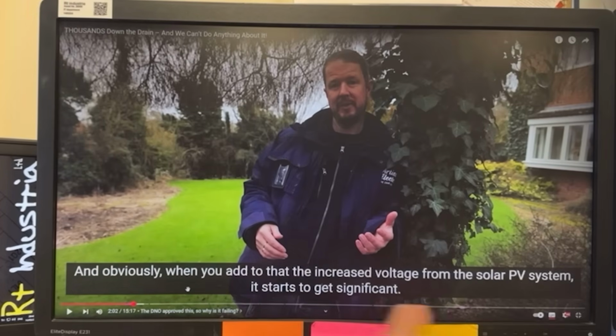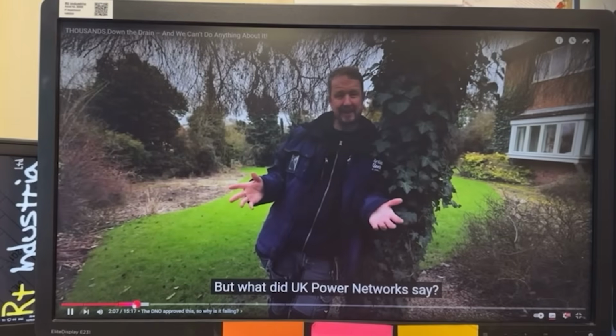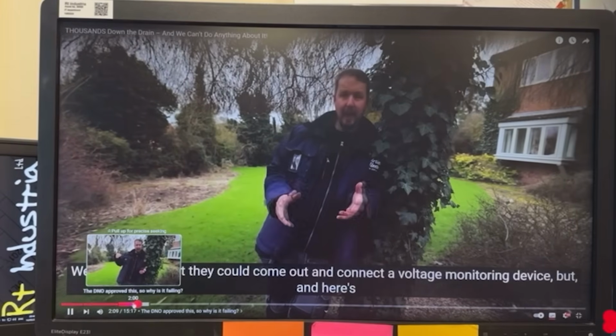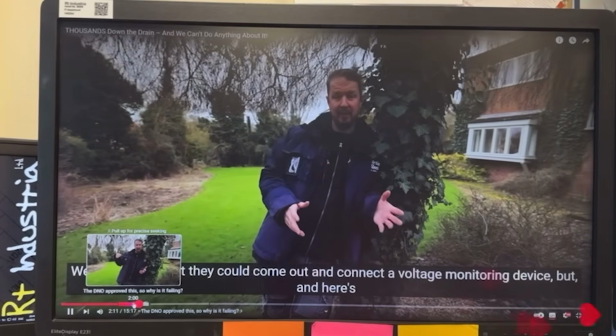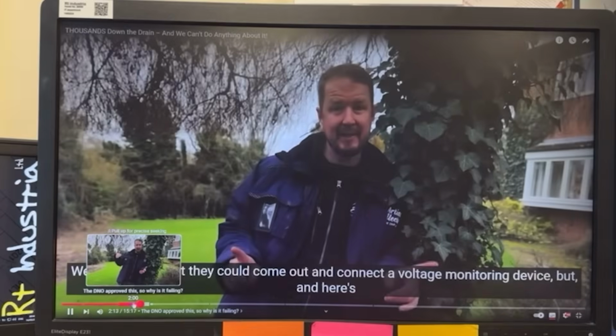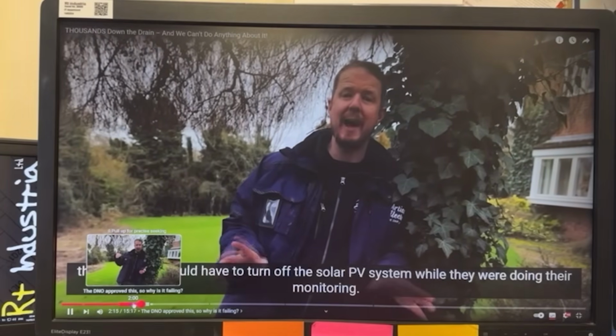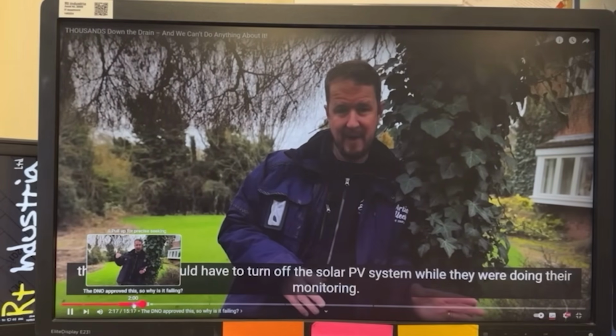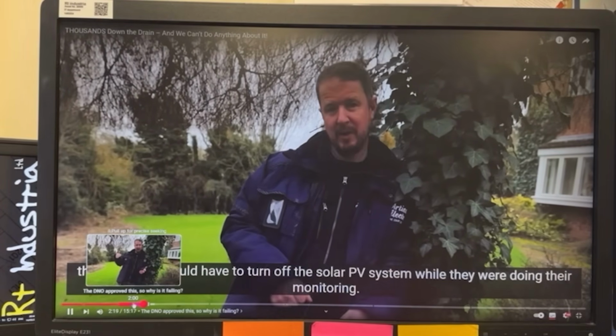I don't know what this means. What did UK Power Networks say? Well, they said that they could come out and connect a voltage monitoring device, but, and here's the catch, we would have to turn off the solar PV system while they were doing their monitoring. Of course you would, because you're telling them that they are supplying the overvoltage. So if you don't turn off your solar PV, they can't run their tests to prove what their voltage is.